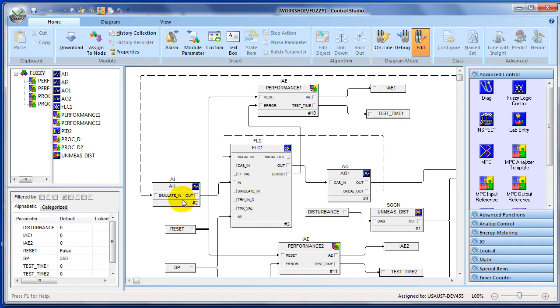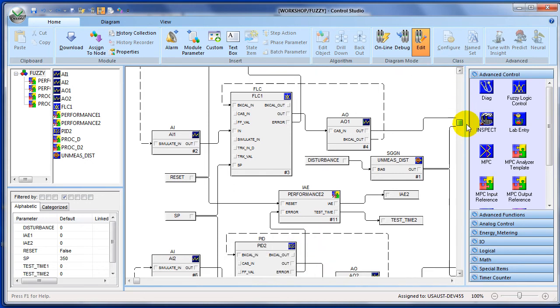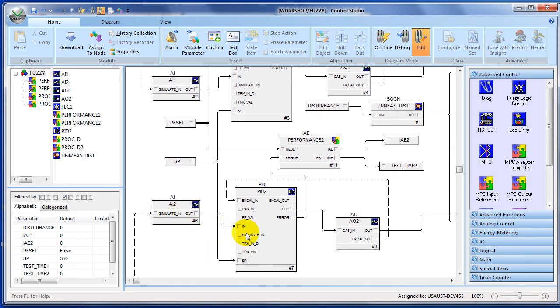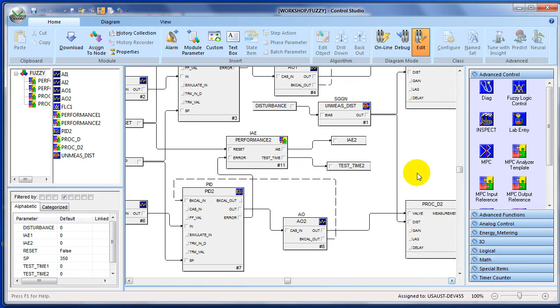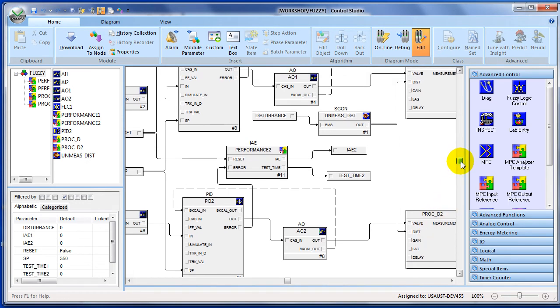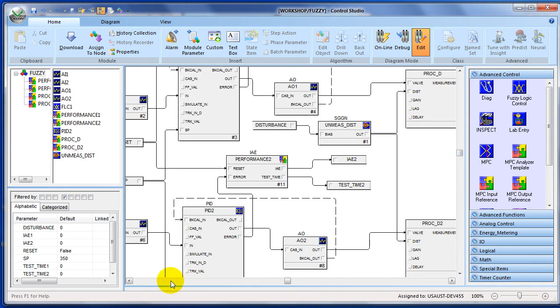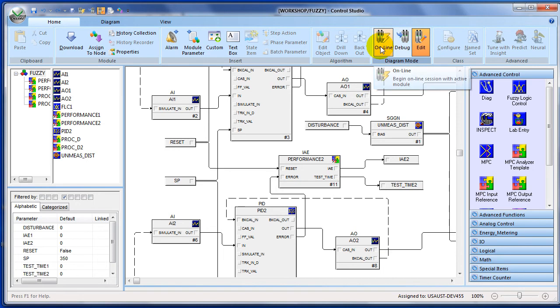This is the module we'll be using in this workshop that has both fuzzy logic and PID. The temperature of both loops is simulated with a dynamic process simulation, and the output is going to the simulation. The error of the fuzzy logic and PID is used to calculate integral of absolute error through a calculation block. We can reset the calculated value back to zero through the reset parameter. The set point to both PID and fuzzy can be simultaneously changed through the set point parameter. The disturbance parameter is used to introduce an unmeasured process disturbance into both processes simultaneously.